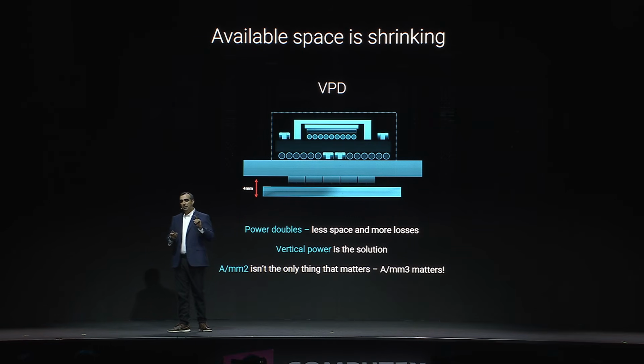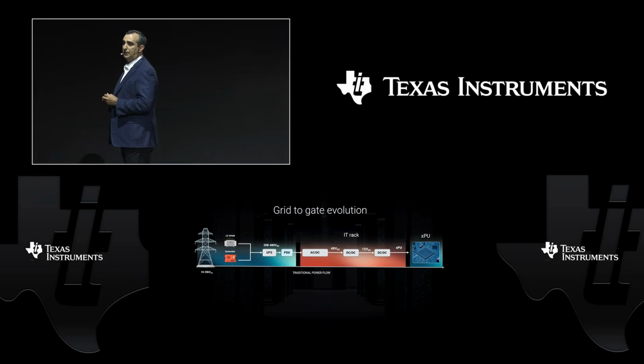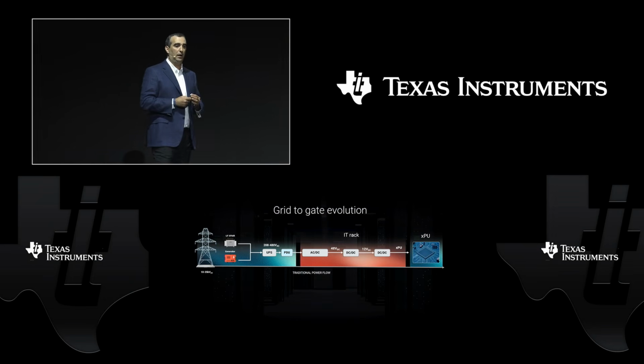So out of necessity, not new ideas or just being neat, the world has shifted to a high voltage DC architecture—either 800 volts or plus or minus 400 volts distributed up the backplane of the rack. This does conceptually solve the current problem; you can deliver 1 megawatt in a rack with an 800 volt backplane.